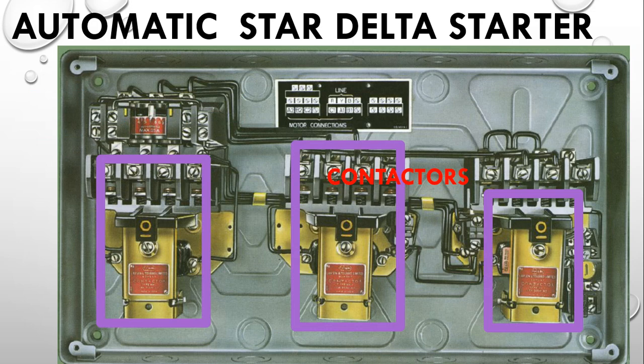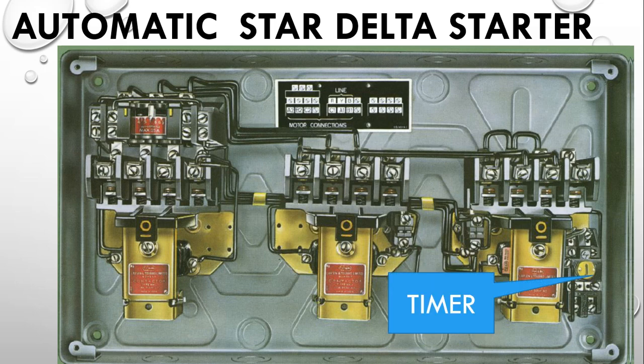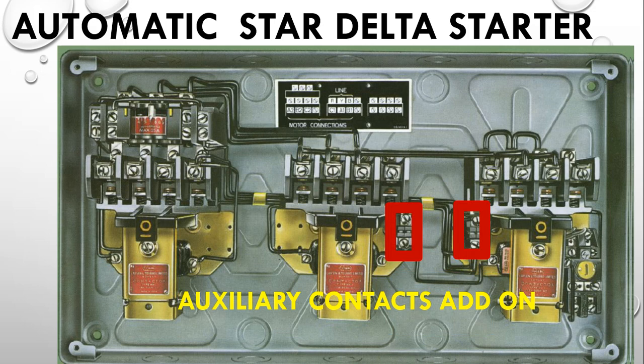The main difference is that this automatic star delta starter has a timer. This timer can be used to set the time when the motor has to change from star to delta. You just press the start button once and release — after the set timing it will automatically shift to delta. Additionally, the contactor has auxiliary contacts, and these add-on blocks provide additional NC or NO contacts beyond the standard four contacts (three power contacts and one auxiliary).